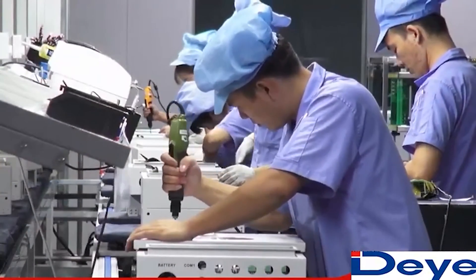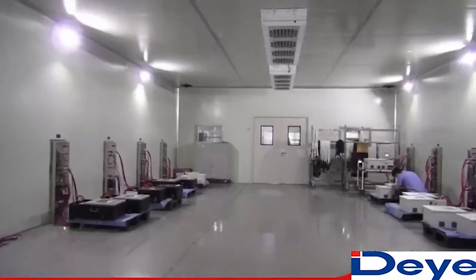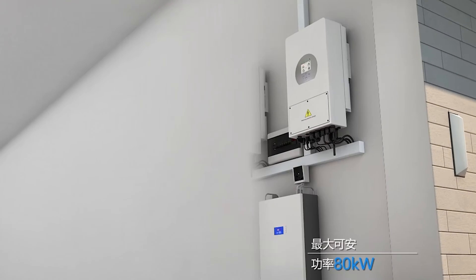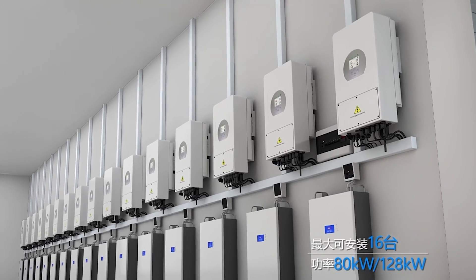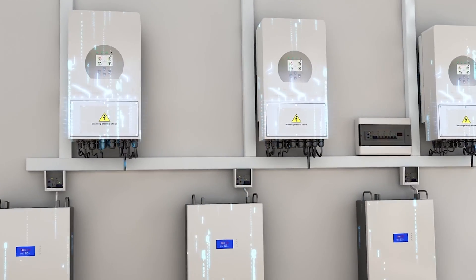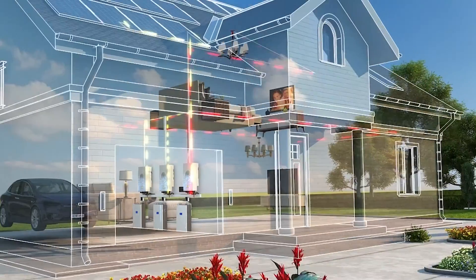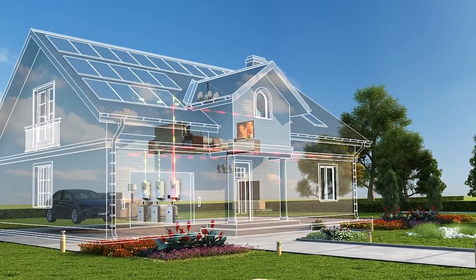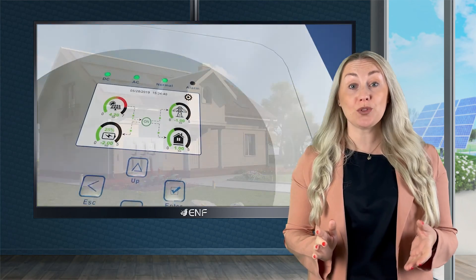Six modes of battery charging or discharging offer flexibility in setting a charging period when the electricity price is low and discharging when the electricity price is high. Multiple protection functions include output overcurrent protection, output short-circuit protection, surge protection, PV string input reverse polarity protection, anti-islanding protection, insulation resistance detection and residual current monitoring units. These protection functions ensure the hybrid inverter's stable and safe operation.